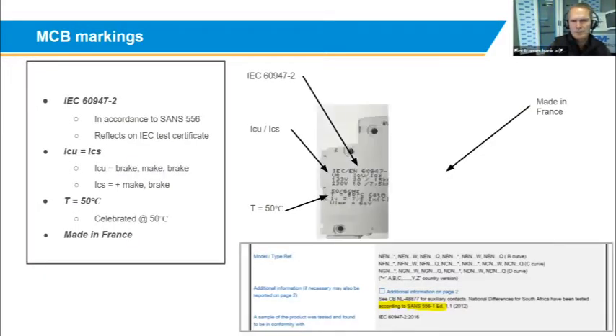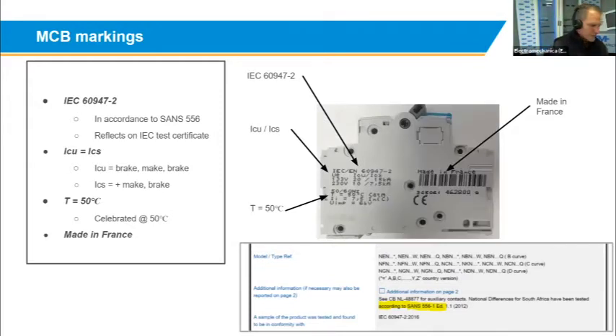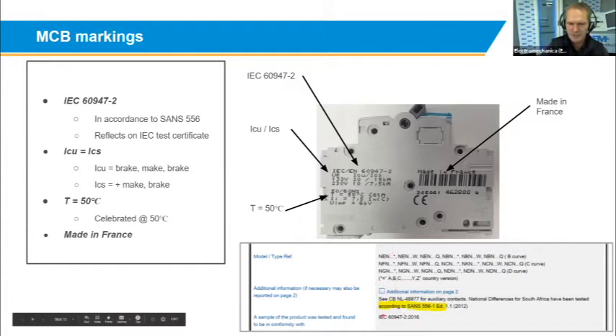Then some more markings on the side of the product. If you take a product, you will physically see that there are markings on the side. These markings are also there for information. You'll see that it says it has been tested to IEC 60947-2. On the test report and test certificate that we get from a third-party independent laboratory, it will state that it's been tested according to IEC 60947-2, but also, the important part, it mentions that it's been tested according to SANS 556-1, which is for the local standards. So that is the IEC 60947-2 with a few amendments to fit the local standards for South Africa.